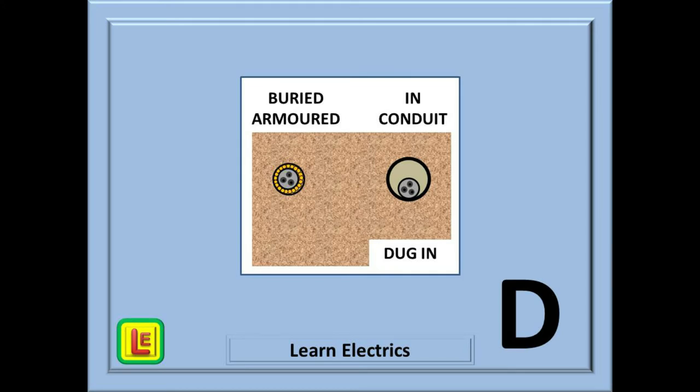On to reference method D. D is for dug in. SWA armoured cable laid directly in the soil is dug in or buried. Cables laid in the ground in conduit or ducting systems are dug in. They are all method D.